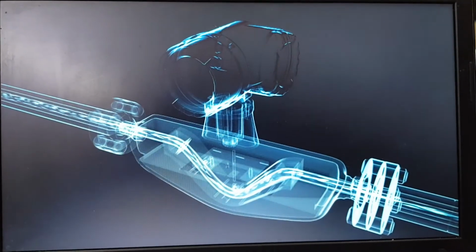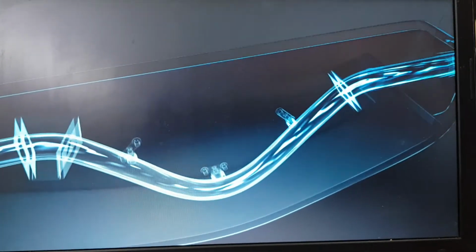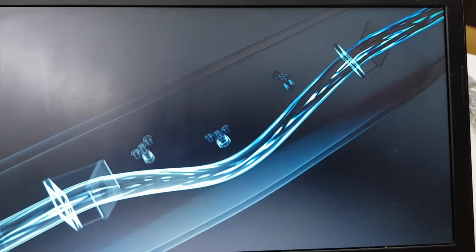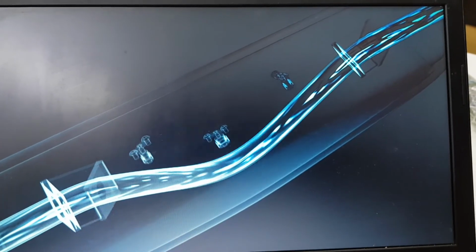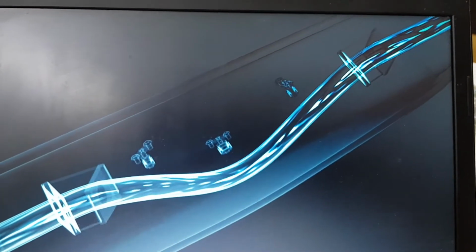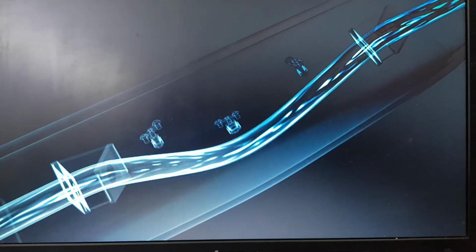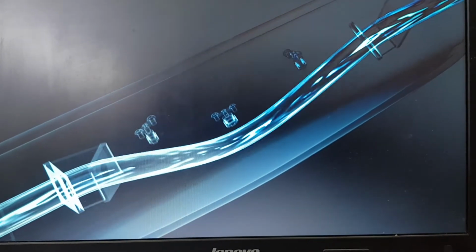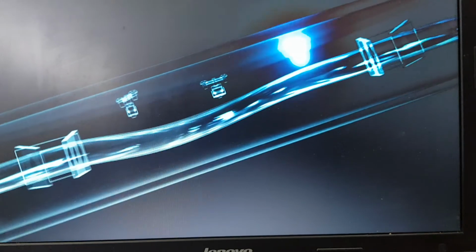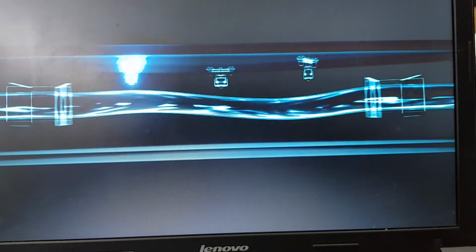Let's take a closer look at how this measurement method works. A tube is located inside each Coriolis flow meter. An exciter causes this tube to oscillate constantly, here in an exaggerated example. If there is no flow, the measuring tube oscillates uniformly. Sensors are located at the inlet and outlet and register this basic oscillation precisely. As soon as the fluid starts to flow in the measuring tube, however, additional twisting is imposed on the oscillation as a result of the liquid's inertia.